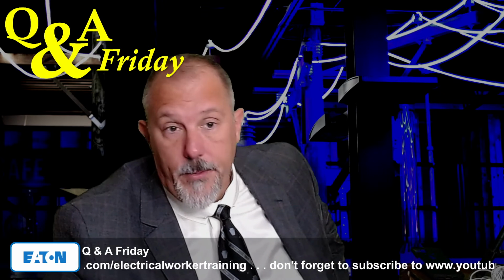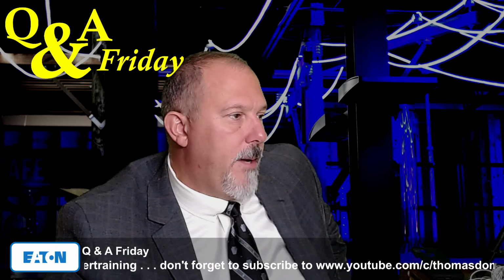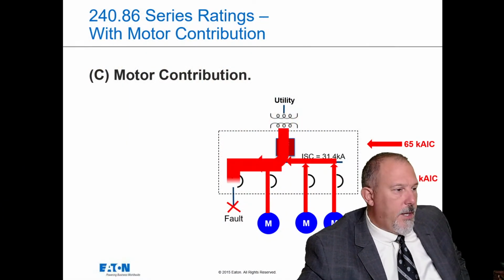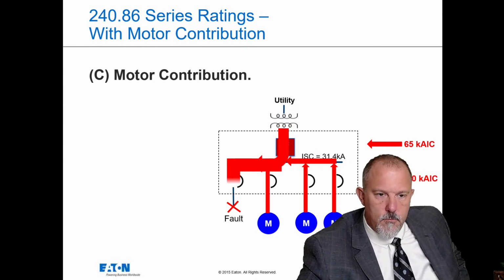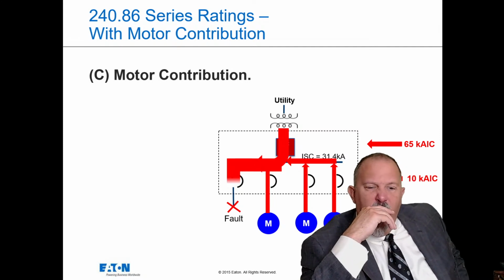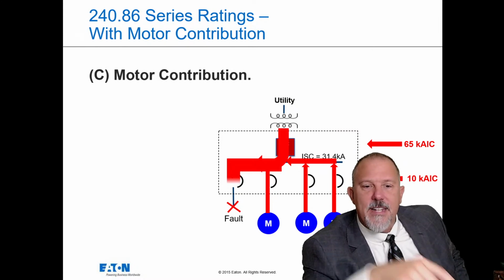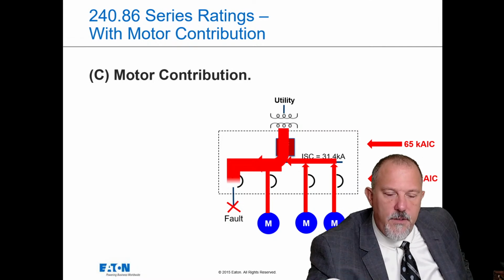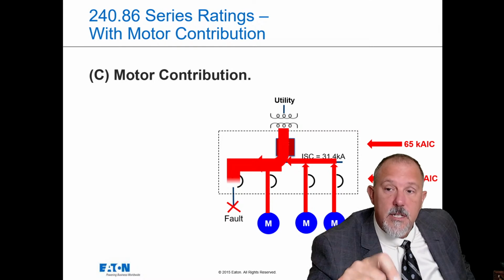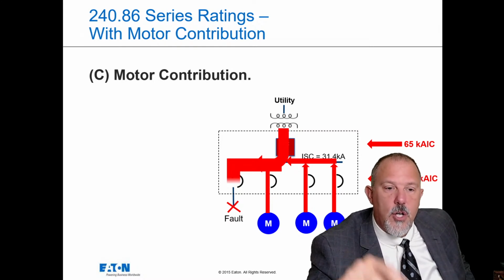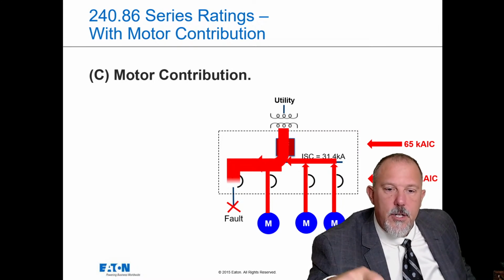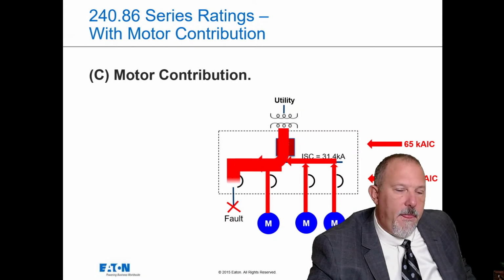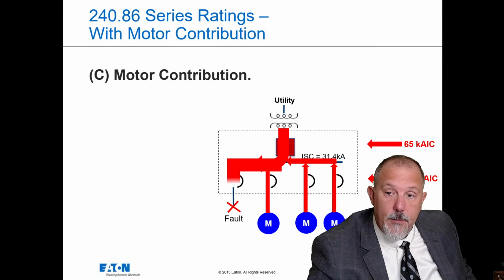Series ratings. I opened the wrong PowerPoint. Okay. Let me look at my motor contribution, and let's take a look at that one. Worth taking a look at. All right, so what we've got here is failure to communicate. So JW says, in the graphics you have shown, where motor fault current contribution affects adjacent circuit breakers fault current, I don't see how 240.86(C) is written properly to address this concern. Instead, it seems to be written to address only a series rated pair at a given motor, or a motor connected in the middle of a series rated pair. That would be correct. I would agree with that, JW.